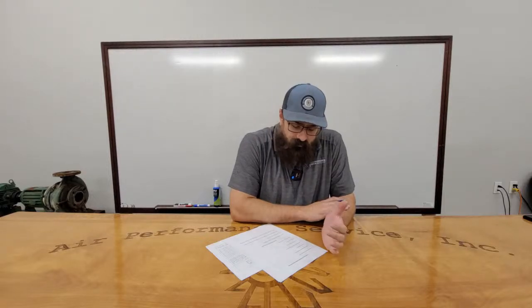I'd say most of them are manual reset if they trip out, right? Yeah, especially if it's a high pressure. I think the low pressures. Yeah, lows won't reset, but the high pressures usually have a manual reset.